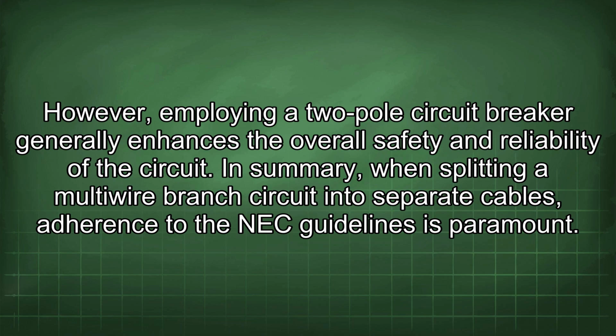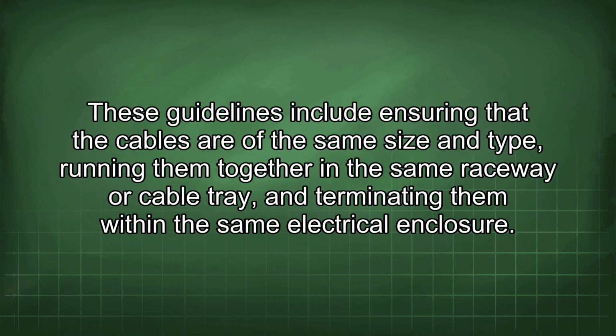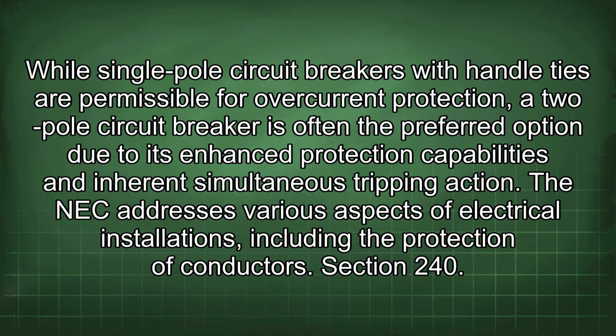In summary, when splitting a multi-wire branch circuit into separate cables, adherence to the NEC guidelines is paramount. These guidelines include ensuring that the cables are of the same size and type, running them together in the same raceway or cable tray, and terminating them within the same electrical enclosure. While single-pole circuit breakers with handle ties are permissible for overcurrent protection, a two-pole circuit breaker is often the preferred option due to its enhanced protection capabilities and inherent simultaneous tripping action.